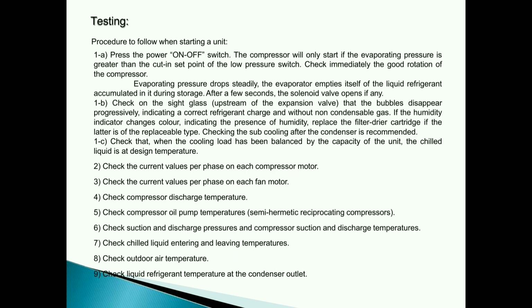Testing. Procedure to follow when starting a unit. 1-A. Press the power on/off switch. The compressor will only start if the evaporating pressure is greater than the cut-in set point of the low pressure switch. Check immediately the good rotation of the compressor. Evaporating pressure drops steadily. The evaporator empties itself of the liquid refrigerant accumulated in it during storage. After a few seconds, the solenoid valve opens if any.